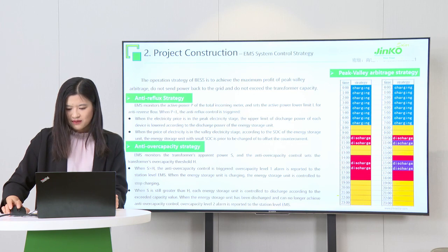For the anti-overcapacity strategy, the EMS monitors the transformer's apparent power S, and the anti-overcapacity control sets the transformer's overcapacity threshold H. When S is bigger than H, the anti-overcapacity control is triggered. An overcapacity level 1 alarm is reported to the station level EMS. When the energy storage unit is charging, it is controlled to stop charging. When S is still greater than H, each energy storage unit is controlled to discharge according to the exceeded capacity value. When the energy storage units have discharged and can no longer achieve anti-overcapacity control, an overcapacity level 2 alarm is reported to the station level EMS.